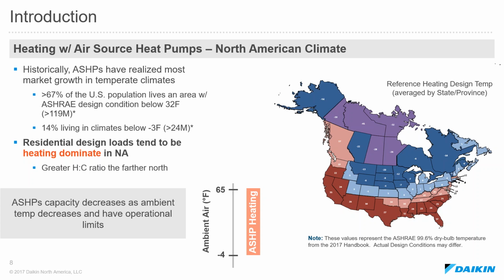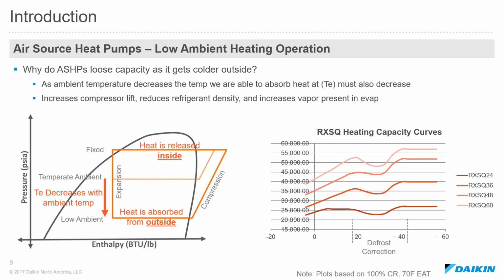And then we're also, like I said, impacted by the ambient temperature. So what that means is we lose capacity as it gets colder out, and that's exactly when we need the capacity the most. So we lose capacity as the load increases. And then we do have limits as far as how cold we can heat down to. So on a VRV Life System, that's going to be -4. So what do we do for some of those areas on that map that are below -4 degrees outside?